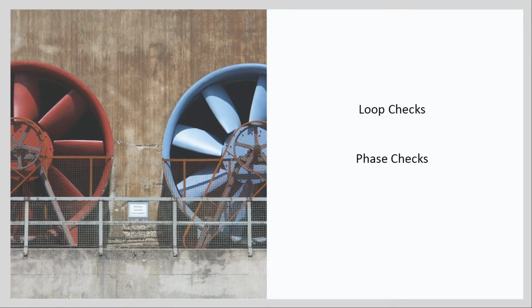So moving on to loop checks, prior to mechanical completion, the construction team would have completed point-to-point checks, or I guess another term would be cold loop checks. So that's the electrical verification point-to-point that all the cables and conductors are terminated to the correct terminal blocks. Following mechanical completion and following energization of the cubicles, we can now move into hot loop checks or operational loop checks.